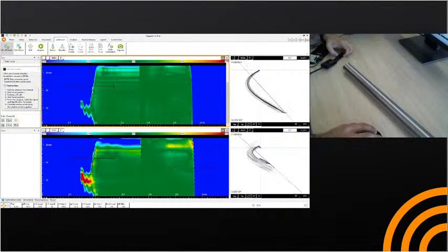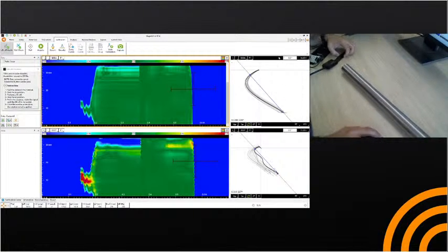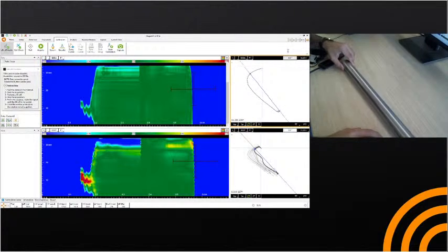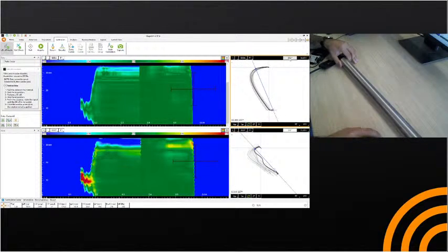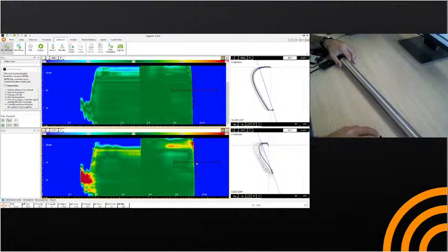So you can see how in the Lissajous view here, there is the render all option. So this means that all the channels that you are seeing in the C-scan are displayed in your Lissajous. So it's simple, just do a rotation for both channels.